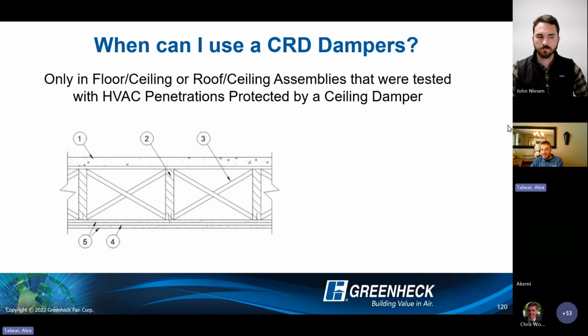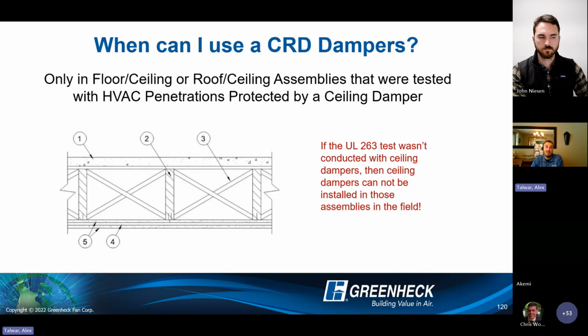So if we see a ceiling design like this that does not show a ceiling damper in it, then we cannot use a ceiling damper in that design. So that's pretty cut and dry. So again, very important to know what your UL design number is. Look that design number up. It'll give you a drawing. It'll give you a listing of what's allowed in that design. You look up something like this, we just see gypsum, we just see truss. We don't see an opening, right? So no dampers allowed if you don't see it in the design.